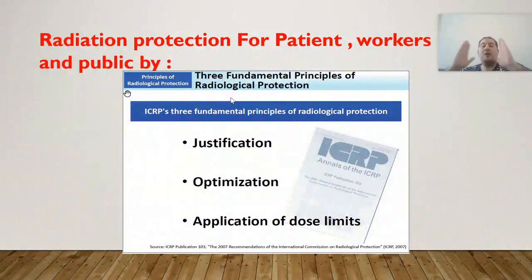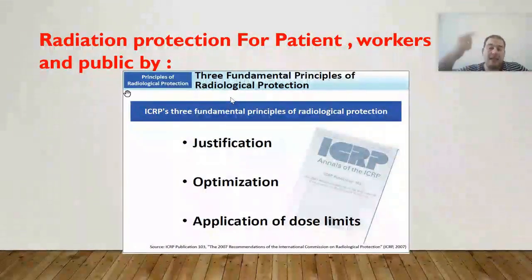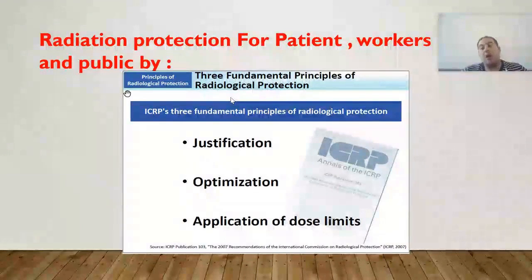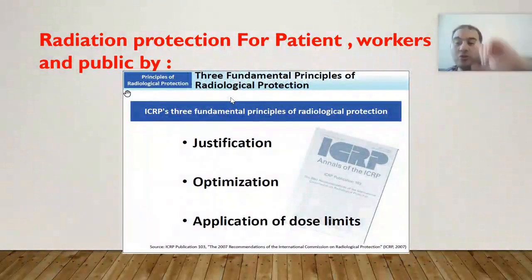I asked the doctor, is the image quality acceptable? He said, yes, it's fine. So we will set these parameters to achieve that image quality. This is called optimization. After 3 years, I conduct another survey to see where I stand in relation to my dose reference level. If I have exceeded it, I will need to establish a new dose reference level from a new high survey, and I will need to repeat the optimization process and the reduction process.